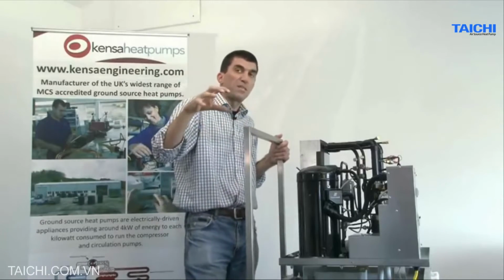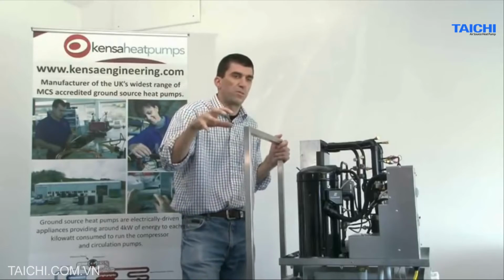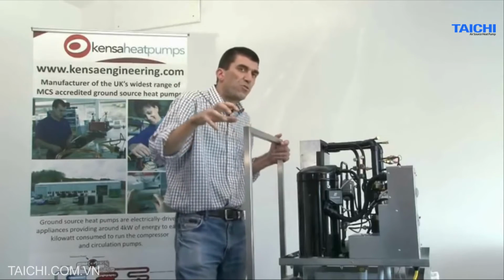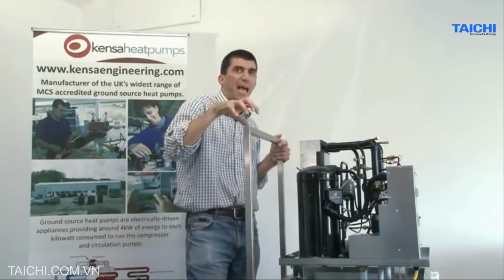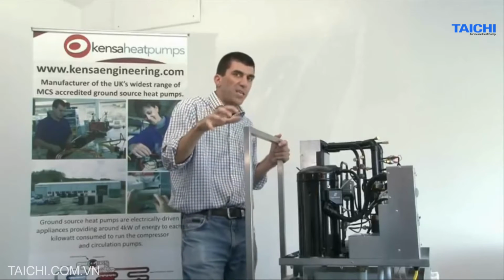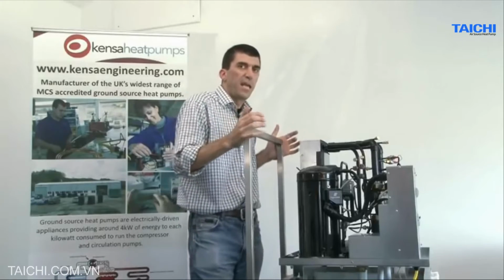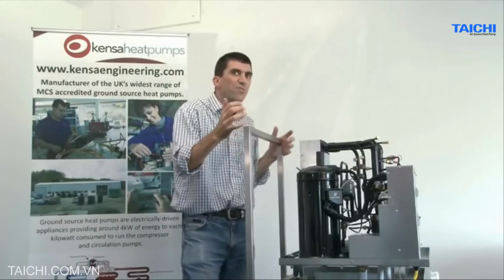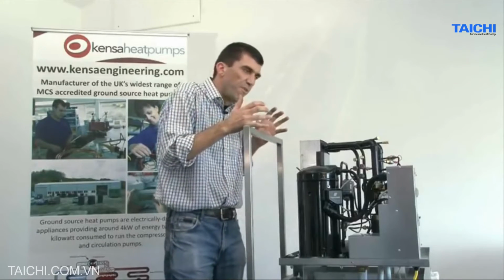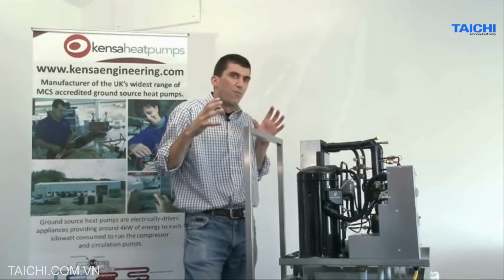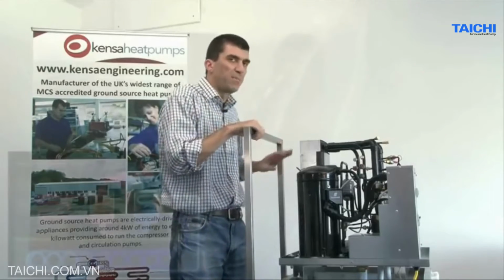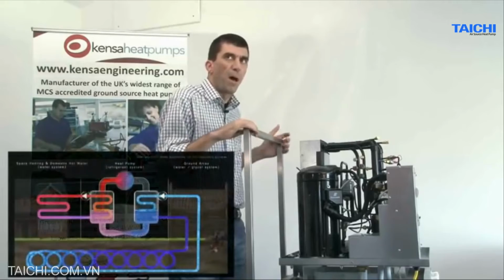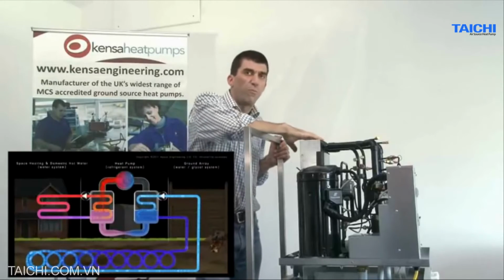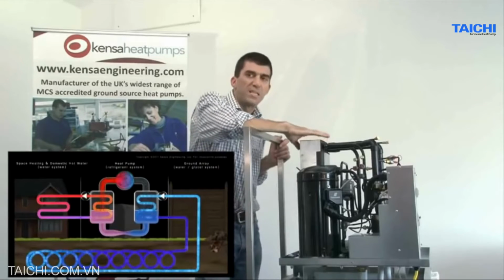At that point, the bottles actually warm up. They have to cool the bottles. Also, you might have seen when you're drawing gas out of a bottle of Calor gas, the bottle gets cold. And that's the latent heat of change of state. The energy required for the gas to boil requires thermal energy, and we exploit that principle within the heat pump to transfer heat energy from our relatively cold groundwater circuit into our relatively warm underfloor heating circuit.